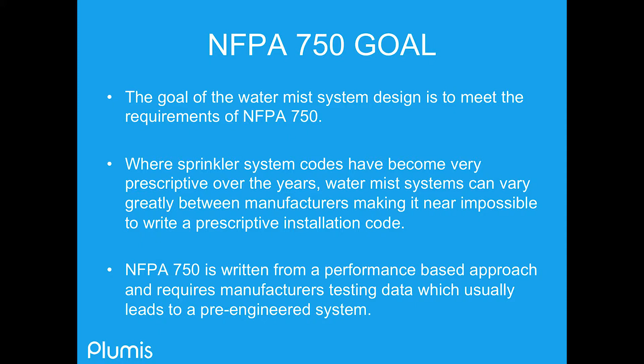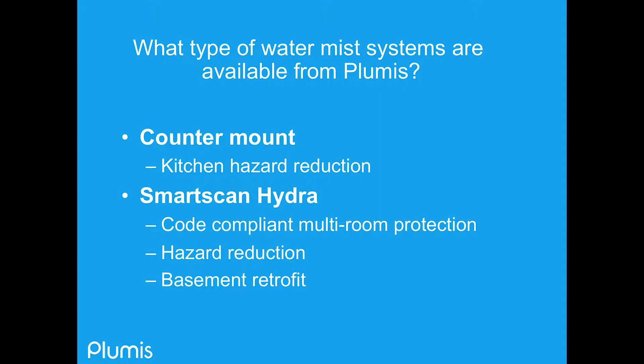We deal with two basic concepts: hazard mitigation or hazard reduction, and code compliance. The first addresses cooking fires, how to put in a suppression system for as little money as possible. We don't have the ability or desire to retrofit the entire flat or apartment, but we need hazard reduction for what we perceive to be the highest hazard, the kitchen. The Smart Scan Hydra is the code compliant system, good for any retrofit, especially basements.